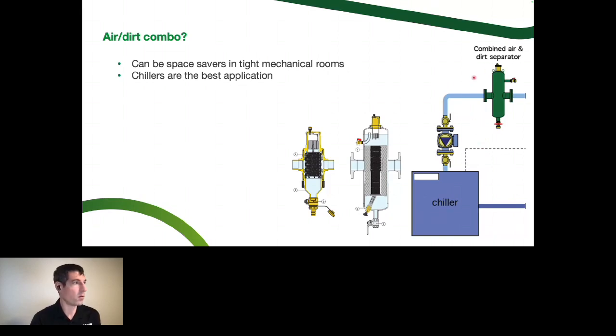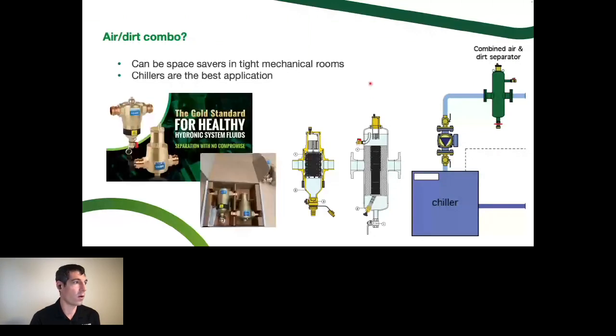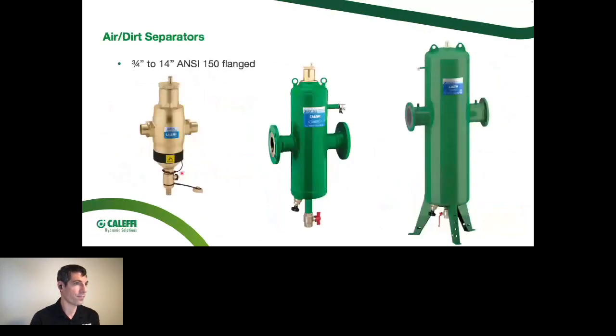In a heating system, if you use a combo air and dirt separator, you're sacrificing the performance of the air or the dirt a little bit. You don't want to catch the dirt after it's gone through the chiller, and you don't want to separate air on the cold return. It's not going to be as effective. So what I would suggest instead is separating them and just getting an air separator and a dirt separator for a heating system and having those in the proper place for best performance. But if you're doing big chilled water systems, this is a good way to go as well.